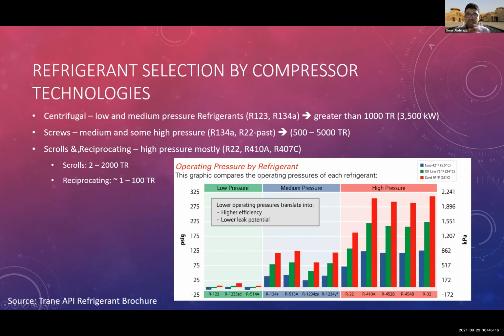All right, so how do we select the refrigerant? It depends mainly on the compressor technology. Is it a centrifugal compressor, a screw compressor, or a scroll or reciprocating compressor, or even a rotary compressor? When we talk about central air conditioning applications, like a centrifugal or large air conditioning machines greater than 1,000 ton, then we use what we call low and medium pressure refrigerants. Examples include, as a baseline, R123 for low pressure and R134a for medium.